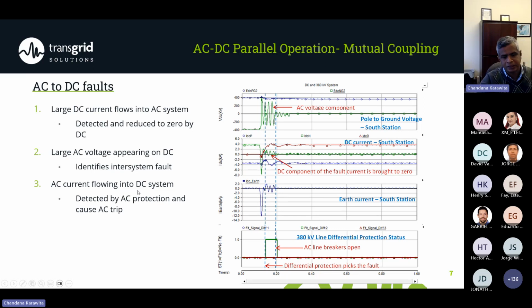And then the last issue was the AC current flowing to the DC system. Now, somehow we have to control the AC current. So we have to have a special detection mechanism, and then we need to trip both AC and DC as quickly as possible to avoid any damages to the system.